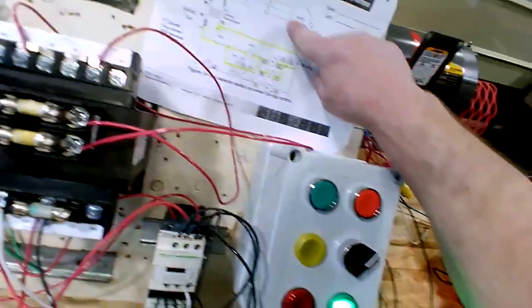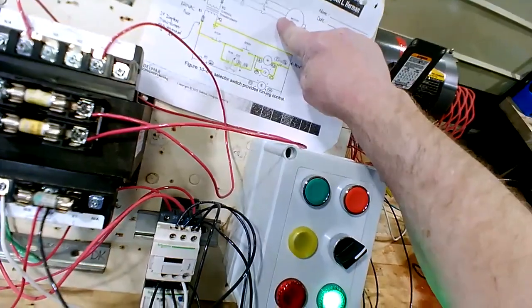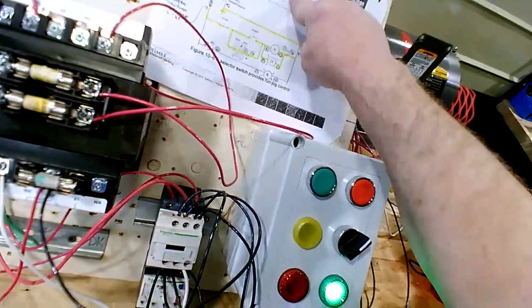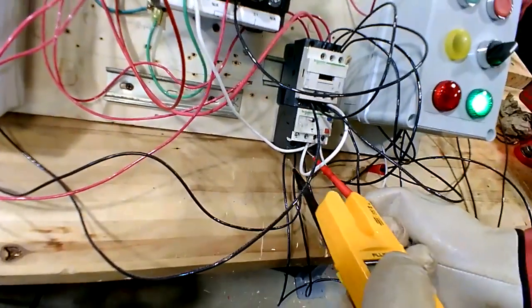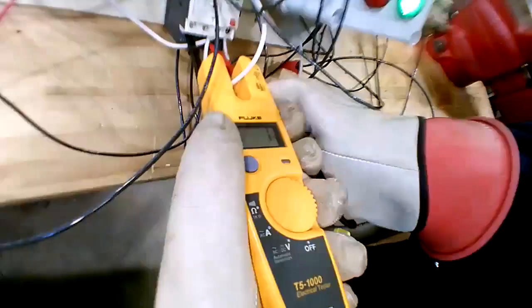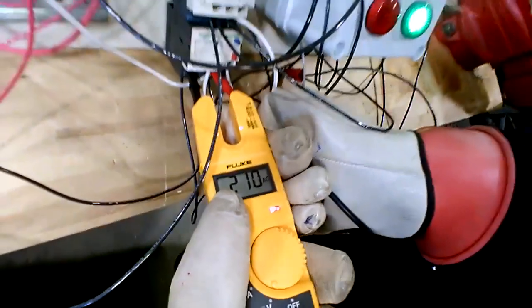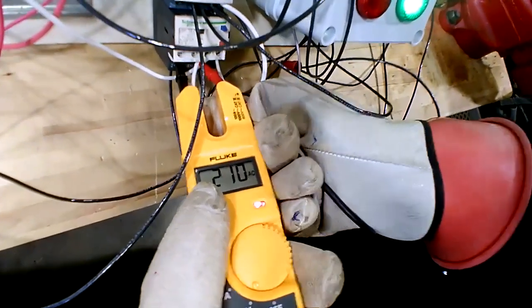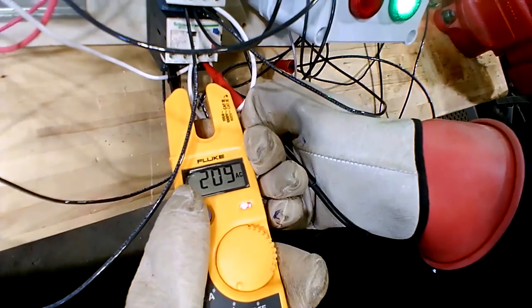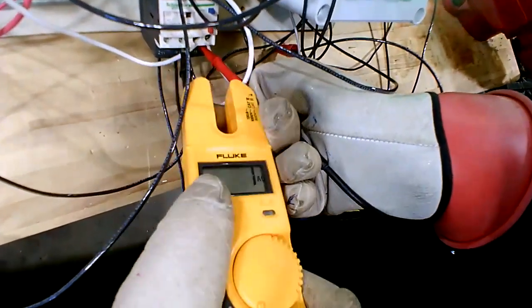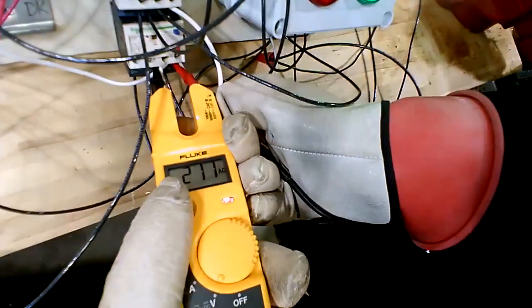Now let's measure leaving the motor. Check each leg phase to phase, go 1 to 2, 1 to 3, and then 2 to 3, where it leaves the motor. 210, that's checking 1 to 2, now go 1 to 3. Good, and then 2 to 3. Good. Now check each one of those to ground.